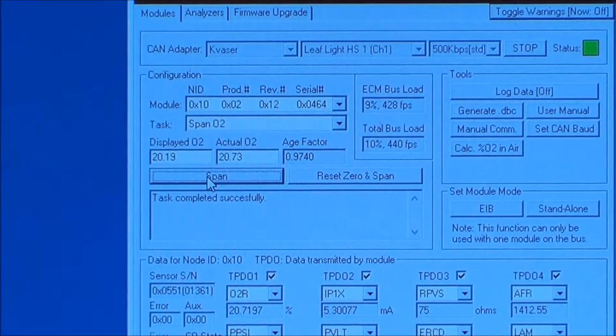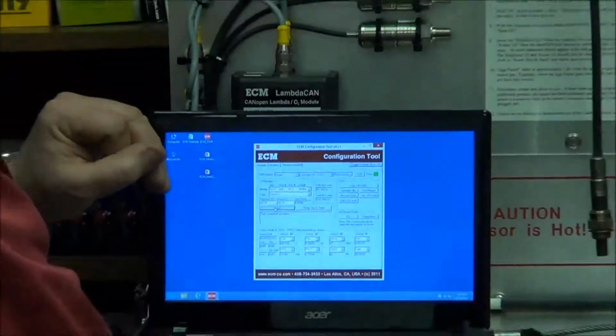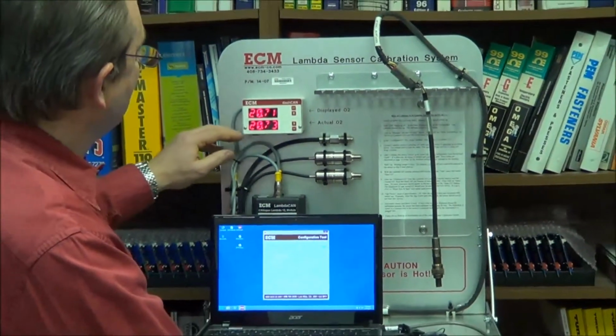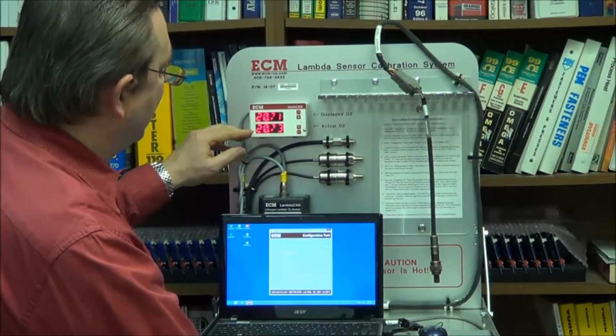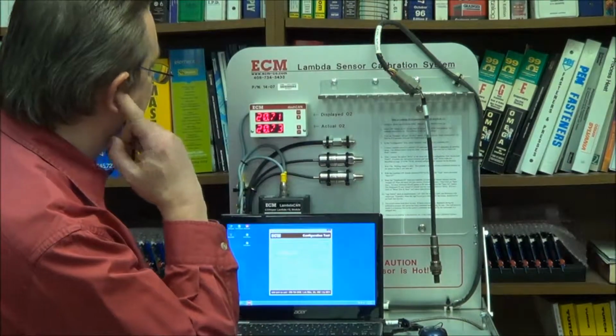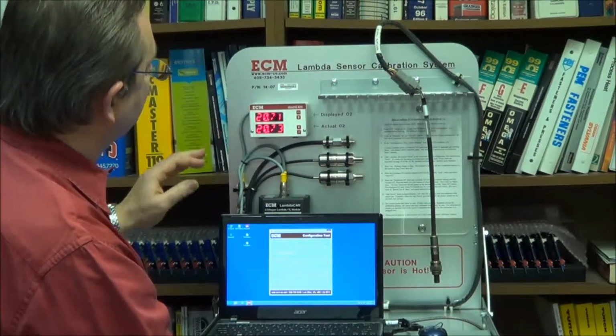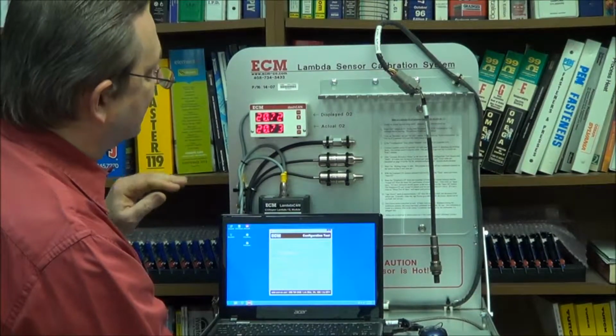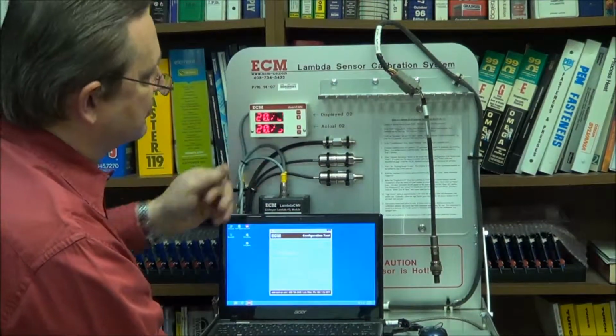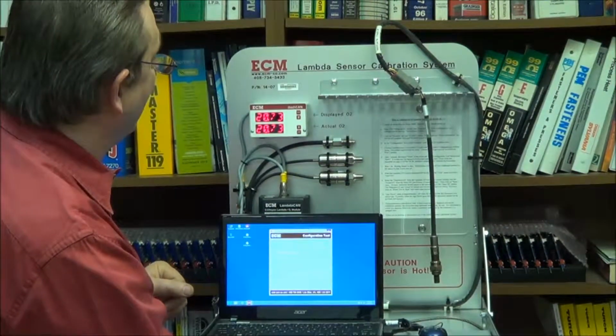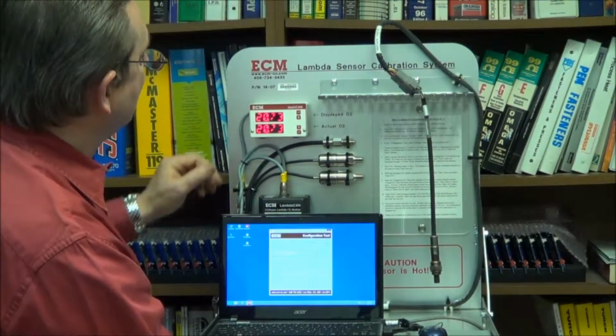What it does is it performs a span on this sensor using air of a known composition, 20.73, and then downloads it into the memory chip. And you'll see it's off a little bit. It's hard to get it dead on because the sensor is going up and down and the sensor hasn't been warmed up for 1 hour.